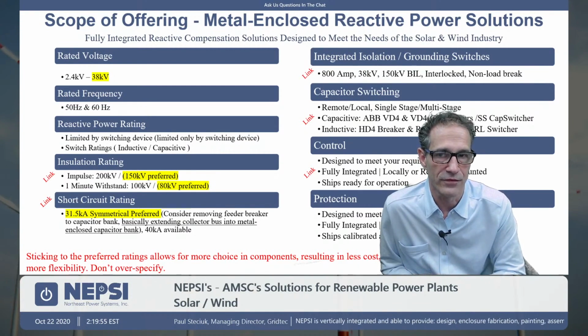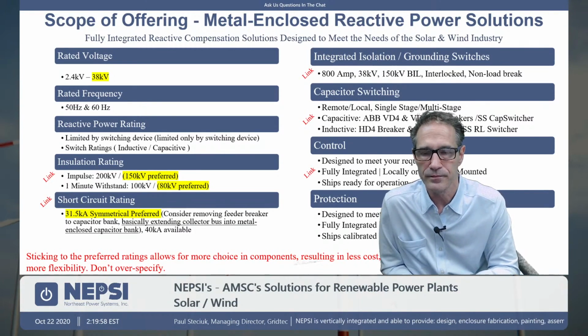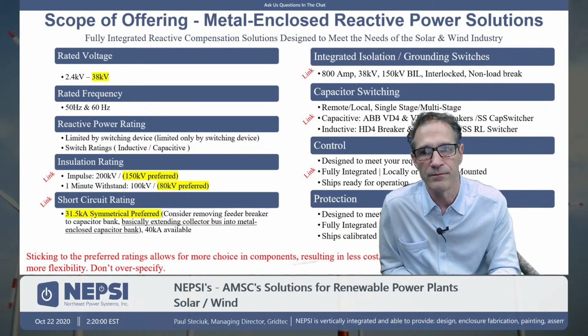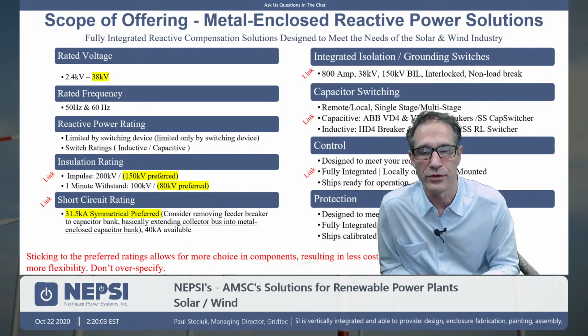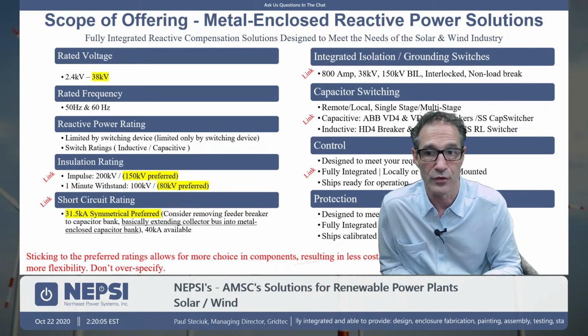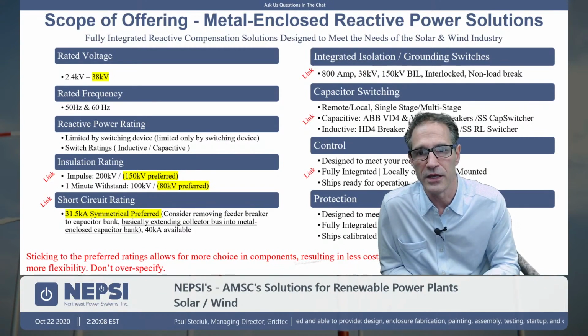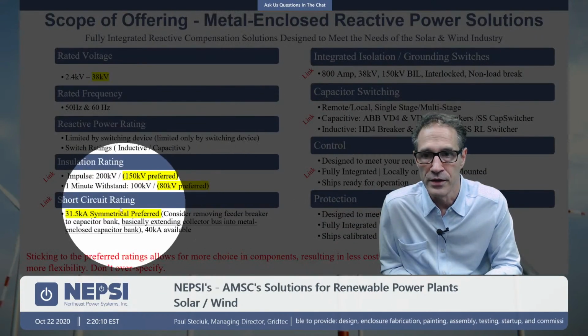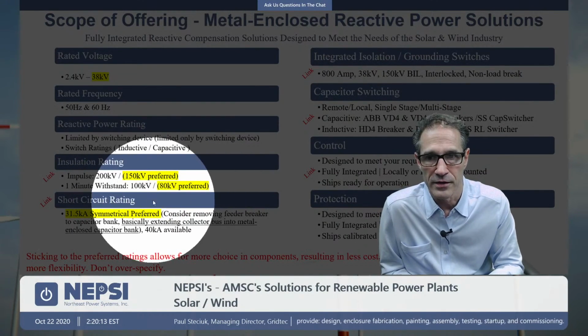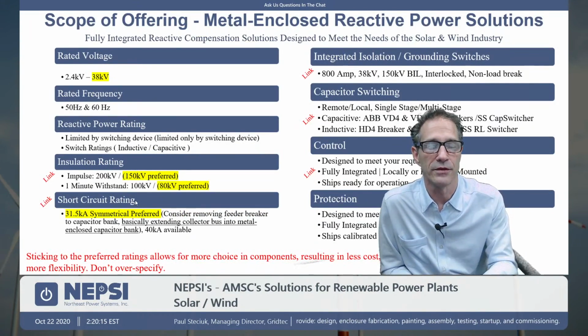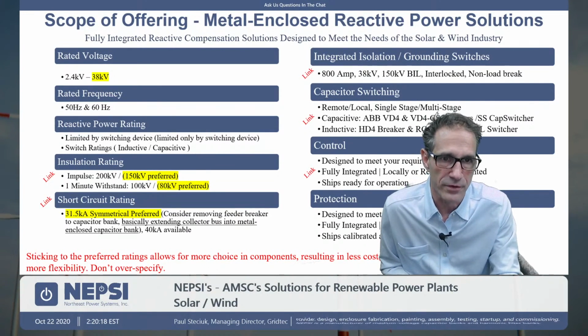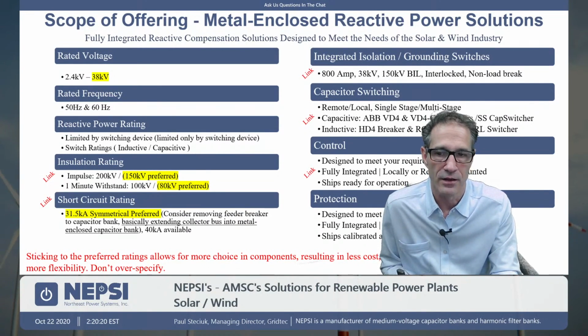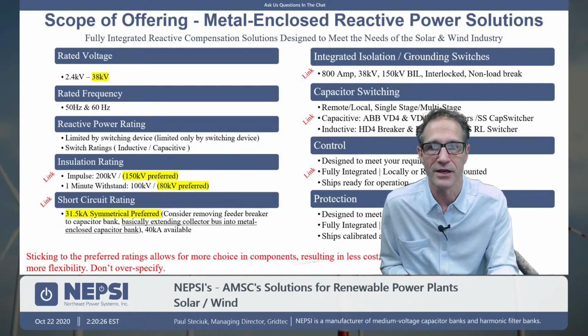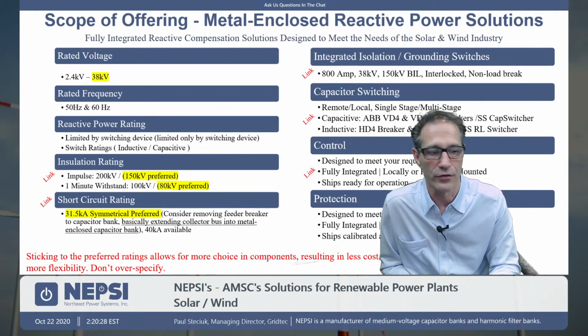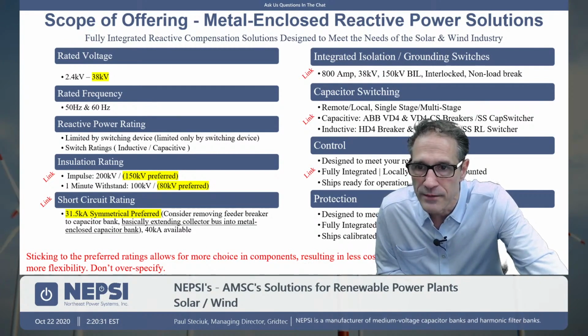In fact, we stock the VD4 and VD4CS here at NEPSI. So by going with 150 kV BIL, you're allowing us to have choice in what we choose, and it also allows us to give you some cost savings. So 80 kV withstand, again, is what we prefer here. The other item to think about is short circuit rating. We oftentimes see the engineering firms automatically specifying 40 kA, and a lot of times we can do the calculations and we see that 31.5 kA symmetrical fault current works for you. So I'm going to talk about why this is important too.